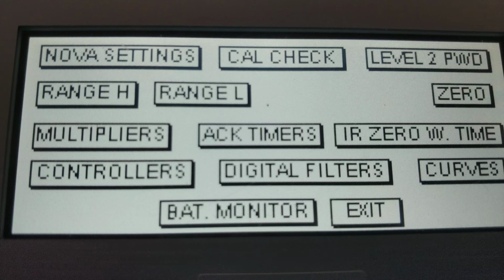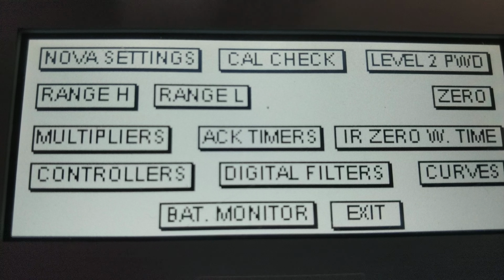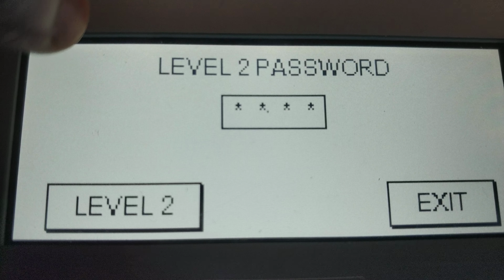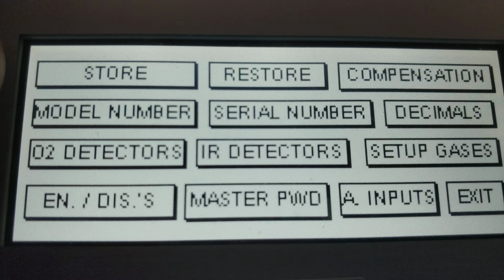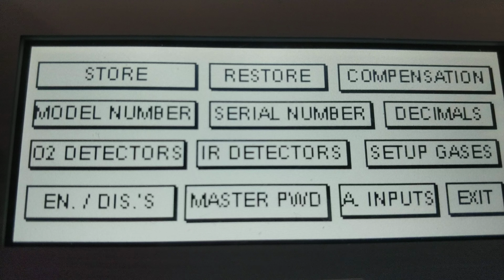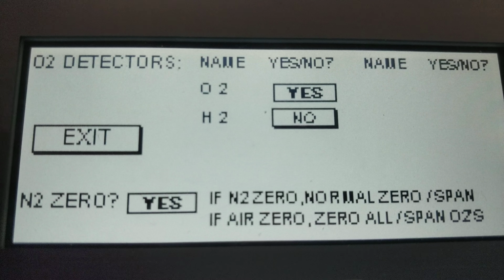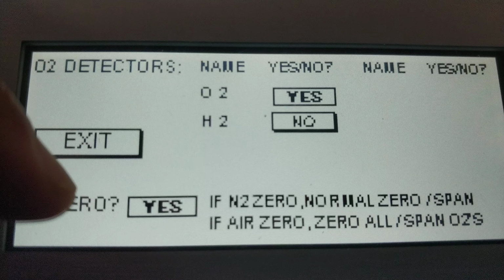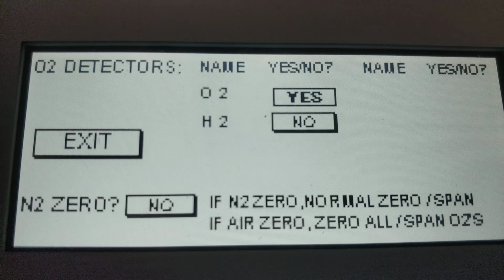So now we need to get into the second level of passwords, and that's level 2 password right here. So I'm going to click that. Password is 2003, so we go 2003, enter, level 2 password. And now what we want to pick is O2 detectors. We want to change this N2 Zero from a yes to a no. So we're going to click that no, make that a no, and then exit, exit.